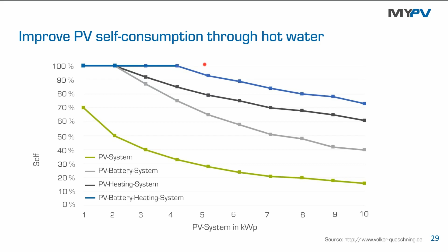Alternatively, you can use an AC ELWA-2, and there you increase your self-utilization ratio even higher at lower investment compared to the stationary battery. But once again, we do not compete with batteries. When you use both systems together, you can expect more than 90% self-utilization ratio for this example. If there is a battery, the battery should have priority before our application. Why is that? It's easy to explain: once it is heat in the hot water boiler by our device, we cannot get back electricity. So again, we cannot reverse the laws of physics, and electric energy has a higher value than heat - that's why our application has a lower priority.